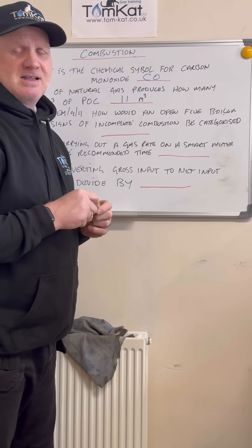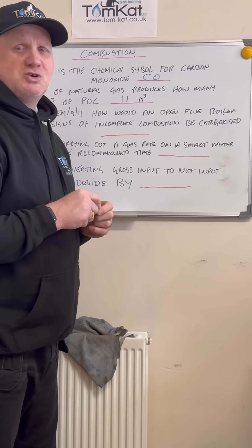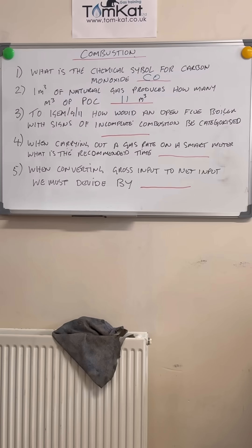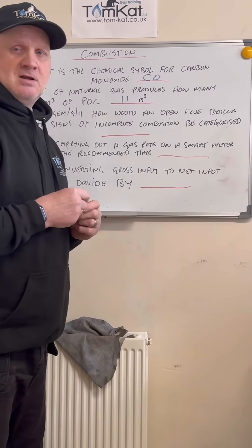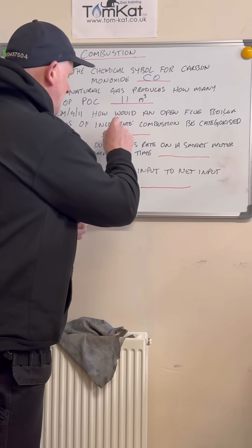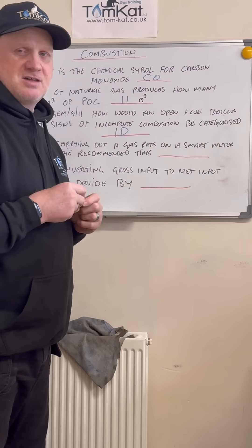Let's look at question number three. To IGEM G11, how would an open-flued boiler with signs of incomplete combustion be categorized? Well, hopefully you said ID — immediately dangerous — not at risk.